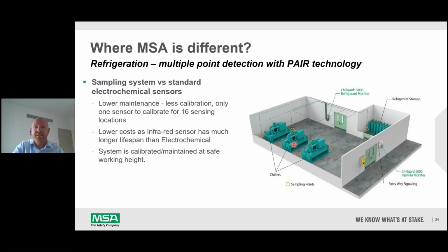So sampling technology is different than electrochemical sensing technology, because if we were using point detectors, we would have to have, for this example, 1, 2, 3, 4, 5, 6, 7 separate detectors with 7 separate sensors. But in a sampling system, it's just one sensor connected through tubing to each of these different locations. So only one calibration annually is required, where for the point detectors, for this example, you would need 7 different calibrations. And when it came to replacing the sensors, 7 different sensors would need to be replaced. So there is some cost savings. We'll go for the sampling system as well.